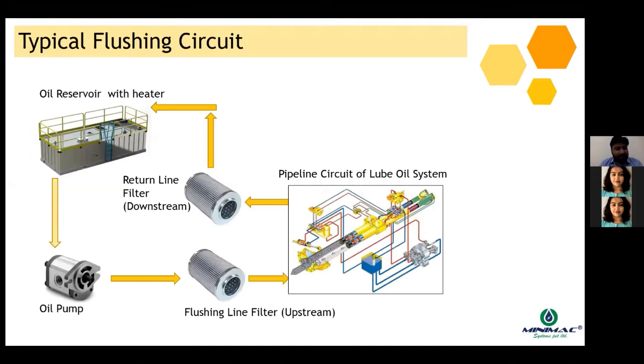So let us see what a typical flushing circuit looks like. It would have an oil reservoir with heater. It would have an oil pump, then the flushing line filter, and the entire pipeline system which you have to flush. Then the fluid goes into the return line filter, and finally it is returned into the reservoir tank.